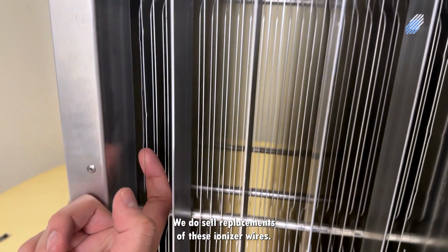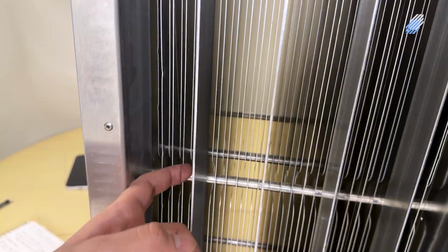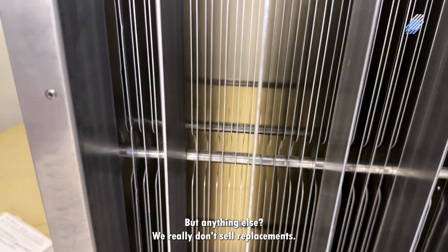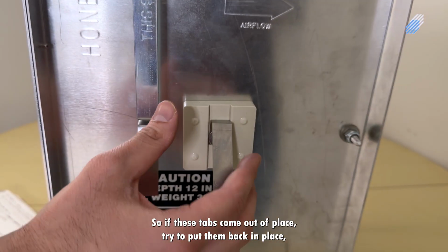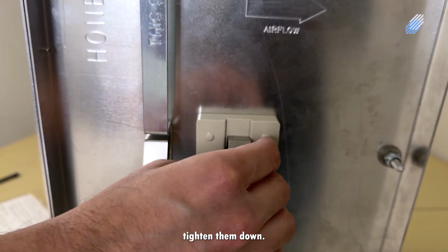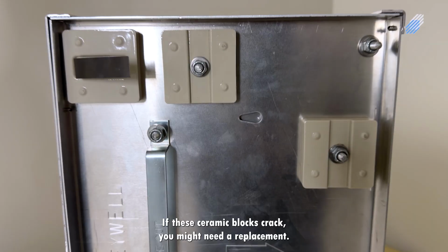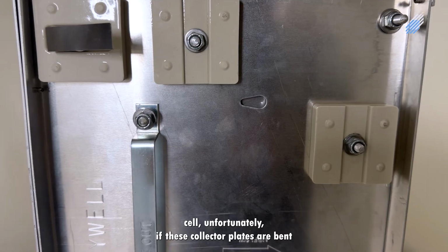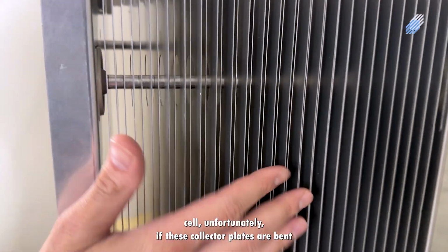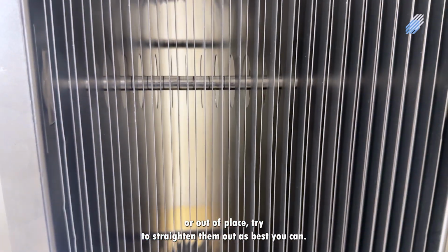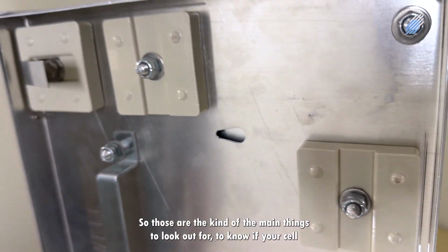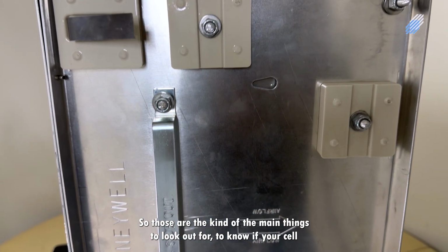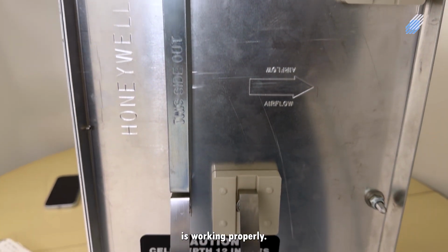We do sell replacements of these ionizer wires, but anything else we really don't sell replacements. So if these tabs come out of place, try to put them back in place, tighten them down. If these ceramic blocks crack, you might need a replacement cell, unfortunately. If these collector plates are bent or out of place, try to straighten them out as best as you can. So those are the main things to look out for to know if your cell is working properly.